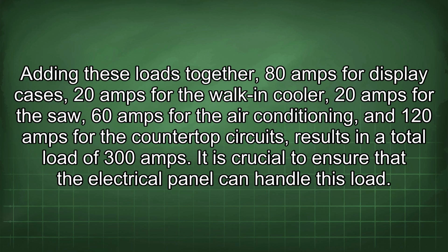Adding these loads together: 80 amps for display cases, 20 amps for the walk-in cooler, 20 amps for the saw, 60 amps for the air conditioning, and 120 amps for the countertop circuits, results in a total load of 300 amps. It is crucial to ensure that the electrical panel can handle this load.